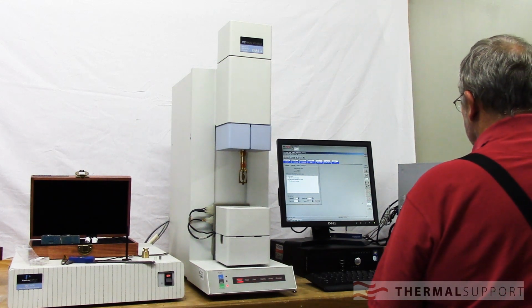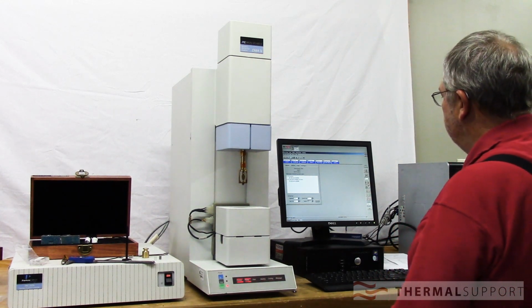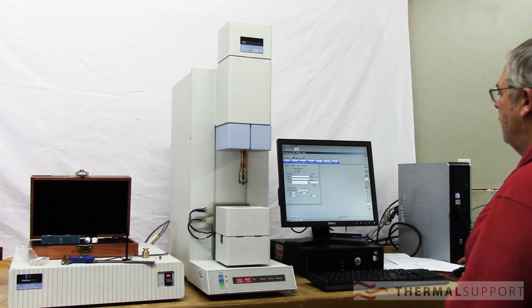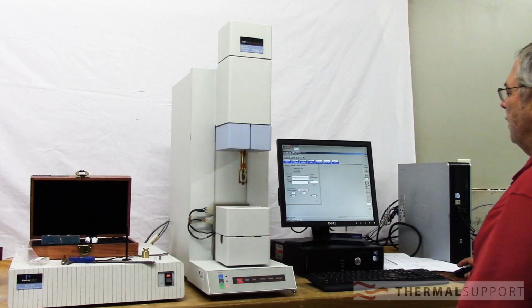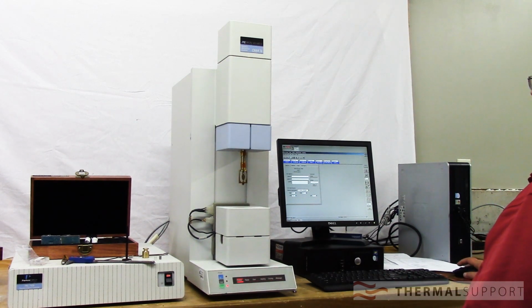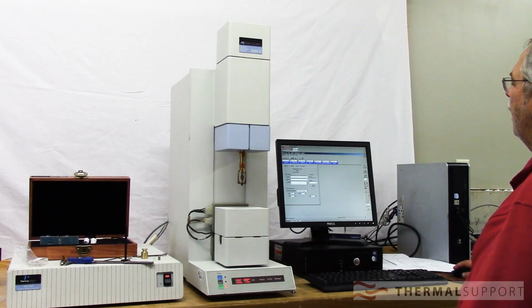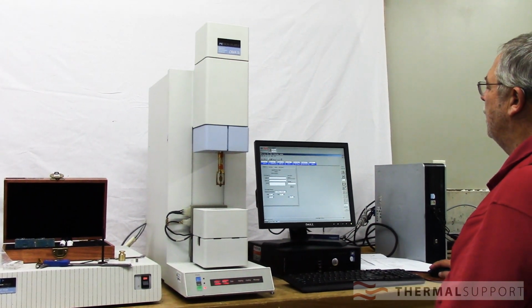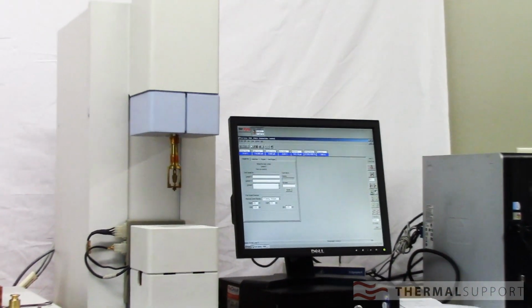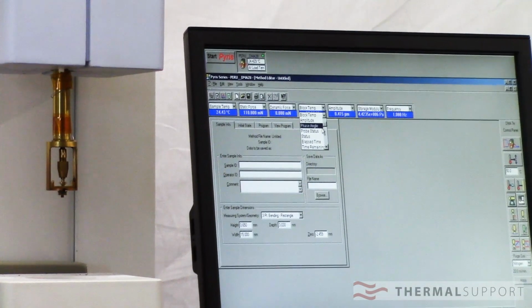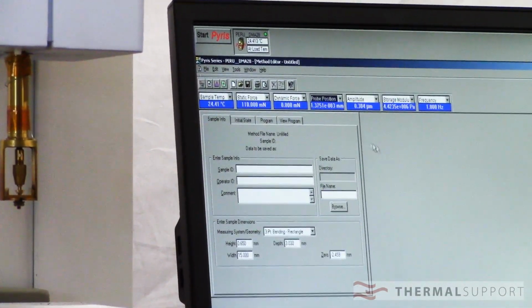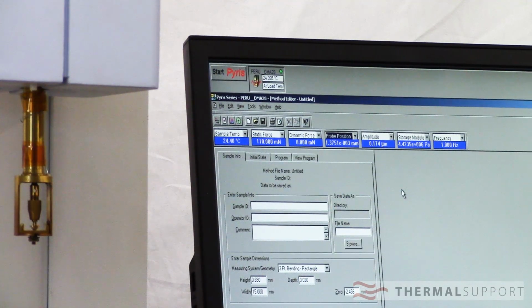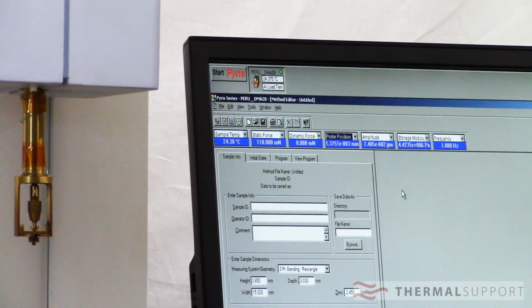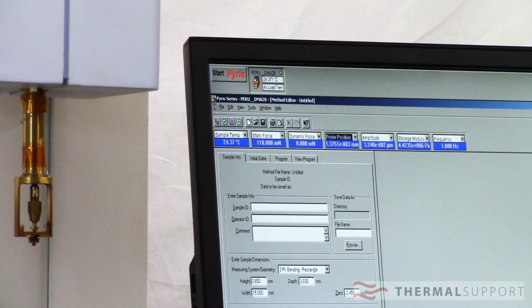Okay? So this time we're going to look at our zero. We did our calibration. That's what we offset with the calibration. So right now, let's see here, get rid of our block temperature. Let's go up here to probe position. So right now we're at 0.001375 millimeters. So it's pretty darn low. And we're right down there where we ought to be.